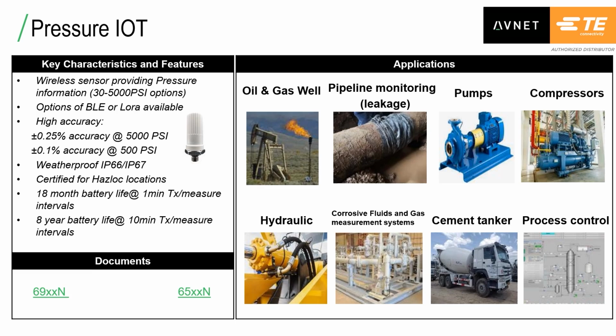Some of the key characteristics and features of TE's wireless pressure sensors include options for either BLE or LoRa communication protocols, battery powered with long life capability, onboard data analysis with programmable actions, intrinsically safe hazardous location certification, pressure ranges from 29 psi to 5,000 psi with digital 24-bit ADC conversion, as low as plus or minus 1% total error band, and excellent long-term stability, as well as wide operating temperature ranges. Some of the key applications for TE's wireless pressure sensors include oil well and pipeline monitoring, corrosive fluids and gas measurement systems, industrial process control and monitoring, refrigeration systems, pumps and compressors, hydraulic and pneumatic systems, smart logistics, agriculture equipment, and energy generation and management.